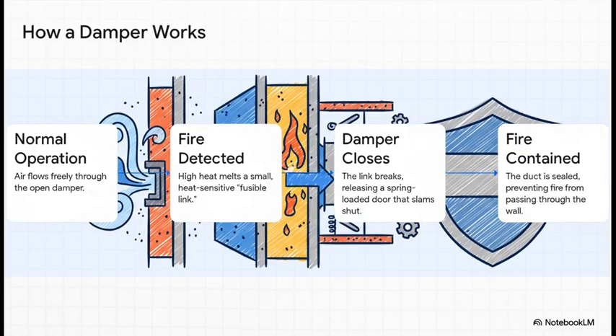The best part is how simple it is — no complex electronics, no computers. Under normal conditions, air just flows right through it. But during a fire, the hot air flowing through the duct melts a tiny piece of metal called a fusible link. That link is the only thing holding back a powerful, spring-loaded steel door. When the link melts, the door slams shut, sealing the duct and containing the fire. It's simple, automatic, and incredibly effective.